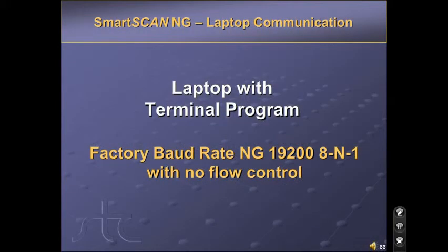To communicate with the system, a laptop running a terminal program set at the correct baud rate is necessary. The baud rate from the factory is 19,200, 8-N-1, with no flow control. If you're using a laptop with Windows 7, the terminal program TeraTerm version 4.69 will work with either the 32-bit or 64-bit Windows.